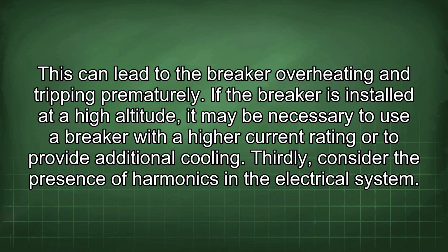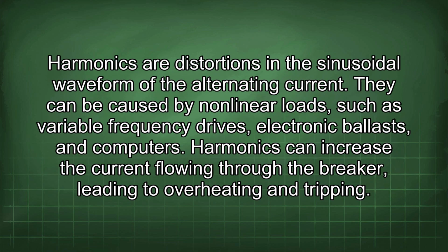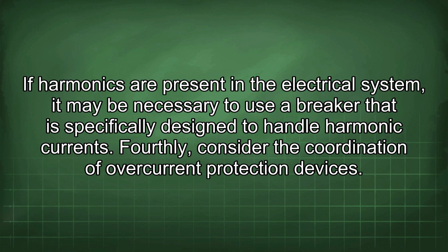Thirdly, consider the presence of harmonics in the electrical system. Harmonics are distortions in the sinusoidal waveform of the alternating current. They can be caused by nonlinear loads such as variable frequency drives, electronic ballasts, and computers. Harmonics can increase the current flowing through the breaker, leading to overheating and tripping. If harmonics are present in the electrical system, it may be necessary to use a breaker that is specifically designed to handle harmonic currents.